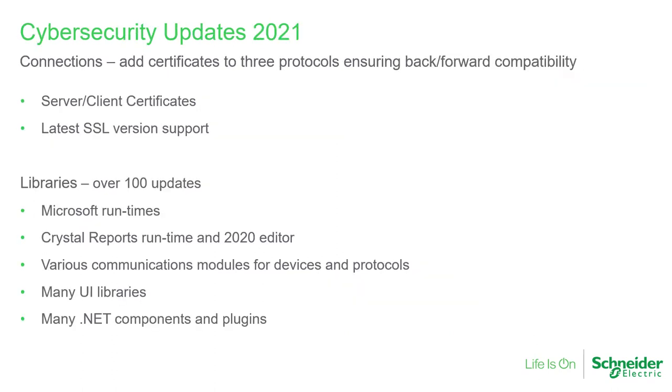New cybersecurity features for Geo SCADA Expert include certificate-based connection security for clients and servers. Now all clients and servers can be protected by the latest TLS or transport layer security protocols. The web services port is now presented through the IIS web server, giving access to the range of IIS features from Microsoft for its security. We also took the opportunity in this release to update many of the libraries used in the product, which improves our security stance. Finally, there are some new options to restrict certain guest and configuration functions. We continue to invest in product security features in our aim for best-in-class capability.